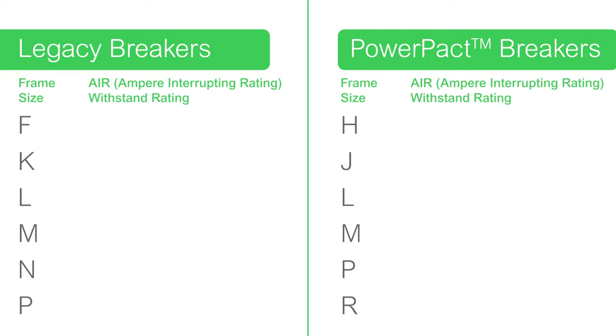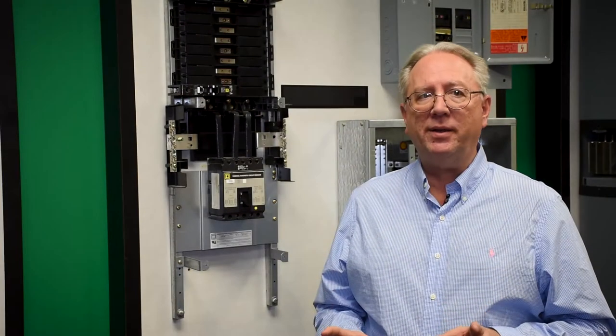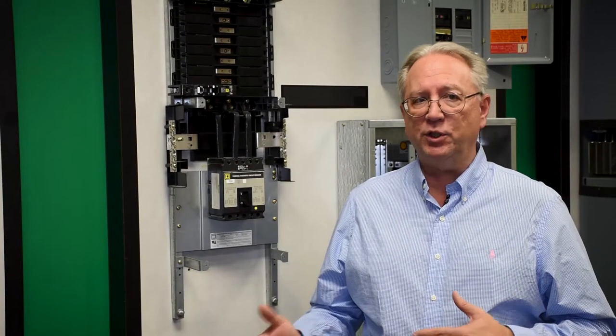You can see from that example that there is a legacy L and a PowerPact L. The second character is the ampere interrupting rating — its ability to withstand the system fault current. On legacy breakers, those characters are A, H, C, etc. On PowerPact breakers, that second character is D, G, or J. So you're never going to have the same combination of legacy versus PowerPact.